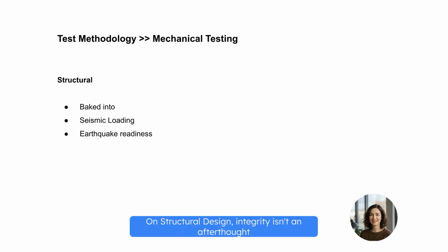On structural design, integrity isn't an afterthought. It must be baked into the entire life cycle, from material selection to manufacturing, to withstand shock, vibration, and pressure. Crucially, for data center deployment, you must account for seismic loading. Do not rely on generic installation methods. Follow the manufacturer's manual strictly, or consult the application engineer to ensure earthquake readiness.